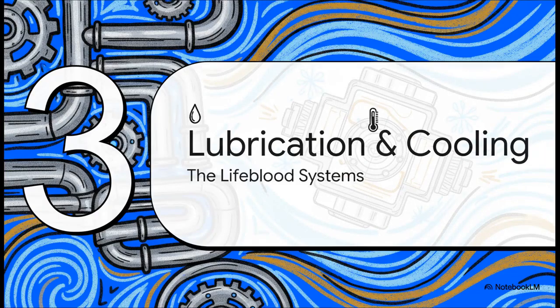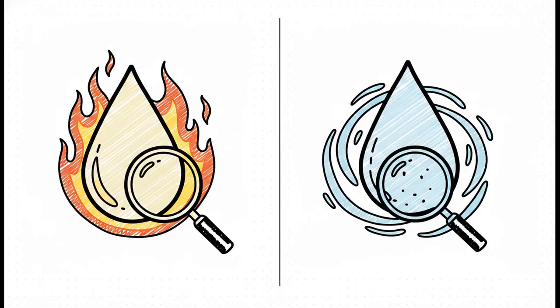Let's move into Section 3 and talk about the lifeblood of this machine, lubrication, cooling, and some strict thermal limits. While fuel is what gives the engine life, oil is quite literally the only thing standing between a smoothly running machine and totally seized metal. And here's the thing, it actually runs two totally independent oil systems that never ever mix. You've got your turbine lube oil, the TLO, which uses a high-end synthetic oil to handle extreme heat and requires a crazy strict lab-level cleanliness standard. Then you have the generator lube oil, or GLO. That uses standard mineral oil because the bearings run much cooler, so it gets a looser cleanliness code.